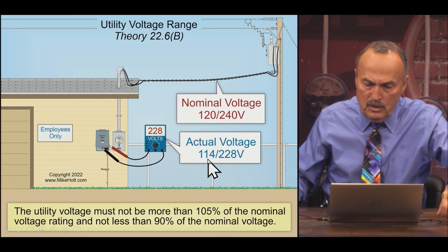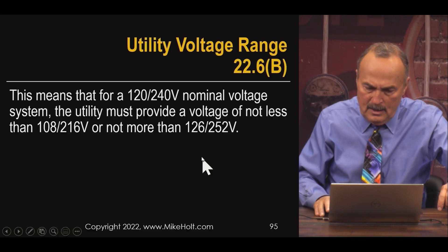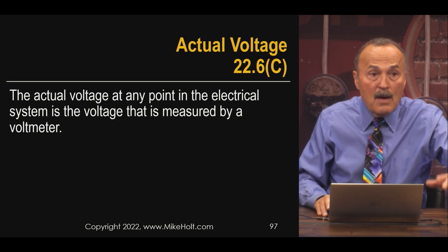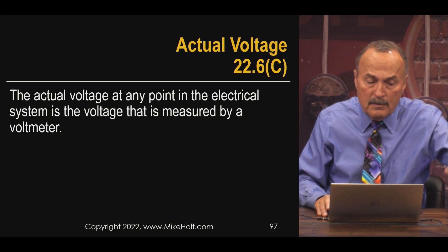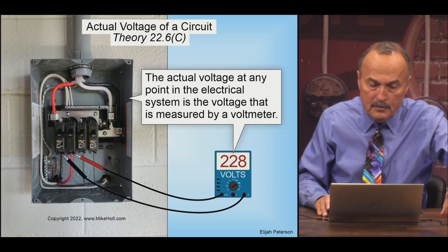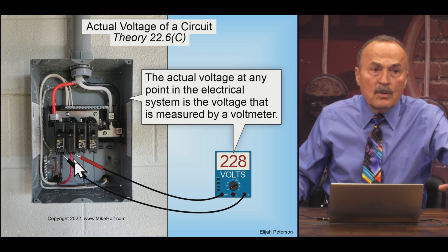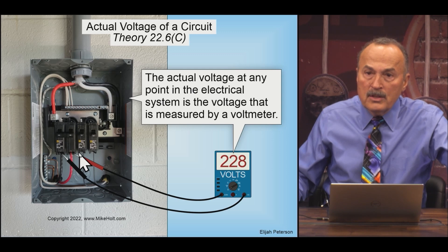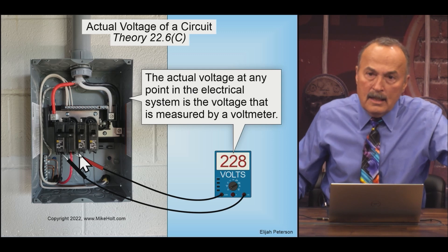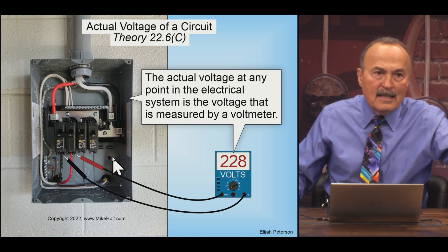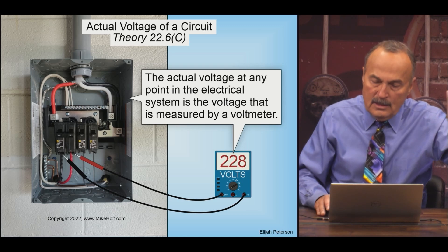The nominal system voltage — the actual voltage would be 108/216 at 90%. This is what electricians are measuring. The actual voltage at any point in the electrical system is the voltage measured by the voltmeter. So you take a voltmeter and it reads 228 — but we don't size the wire and we don't do any calculations based on the actual voltage. We've got to go with, in name only, the nominal system voltage. It could be less, it could be higher, and it's close enough.